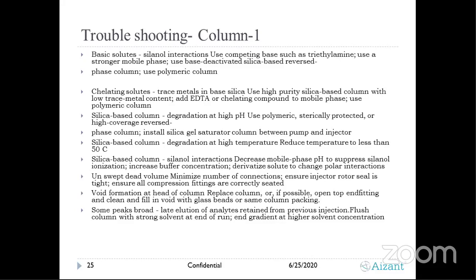Again, there is a recommendation given by the vendors for the columns that you have to operate in a range of 2 to 8 or 2 to 11. So we have to be very specific that whatever method we are using, we should not touch these boundaries. Meaning if the recommendation is 2, you should not go to 2, or if the recommendation is 11, you should not operate at a pH of 11. Always go to a minus 1. Suppose you are using a column which recommends a pH of 2, at least you can bring it to 3. Or for 2 to 11, instead of 11, you can use it at 10. But don't touch the boundaries of the recommendations the column vendor has given. That will end up in extreme challenges: you will lose your chromatography or the column will collapse.